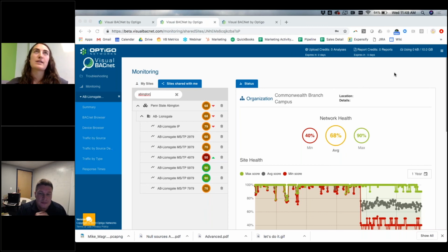Yeah, and another thing that I've seen happen on other campuses is they'll turn in that 20-minute capture, which is great for those 20 minutes, and then there's a problem 5 hours later. So, as you were saying with alarms, the 24 hours of no alarms or few alarms. Yep. Saying that with network as well, it's not just do you have 20 minutes of good network data, but is it consistently staying good?